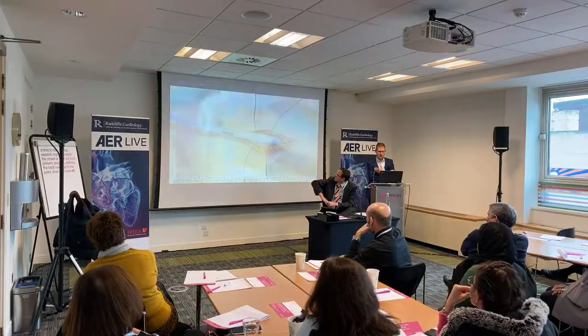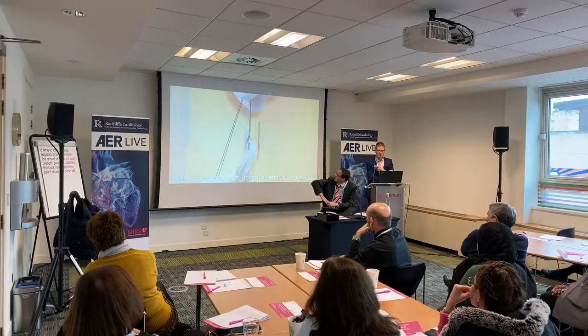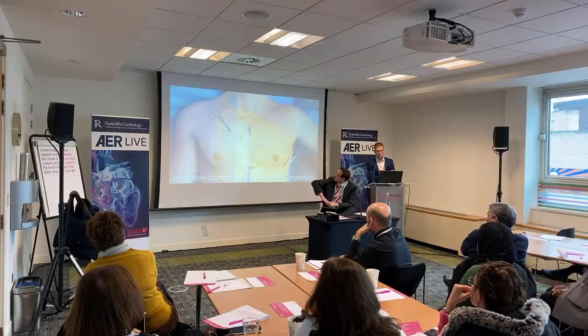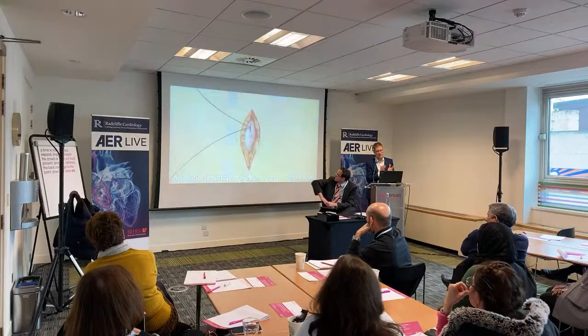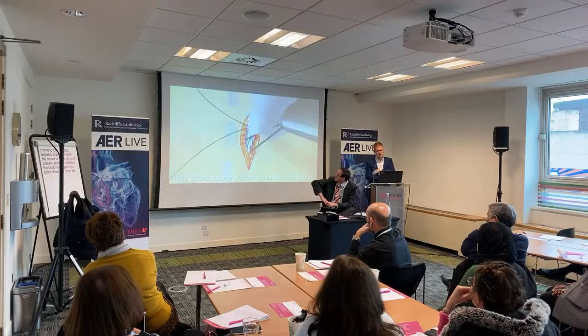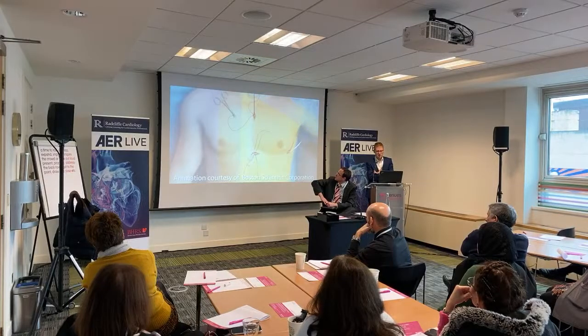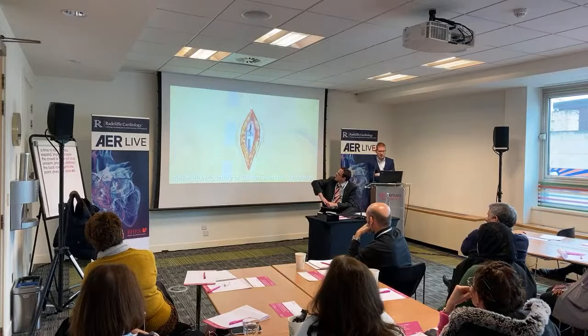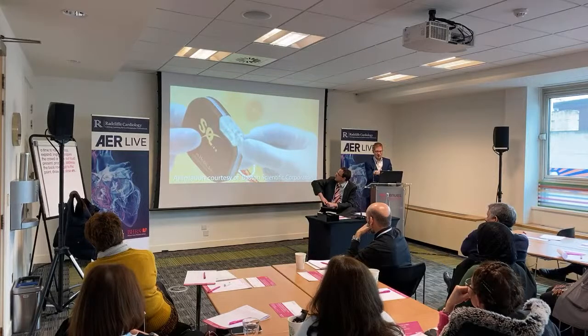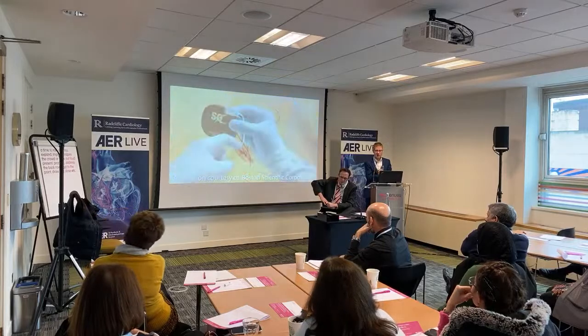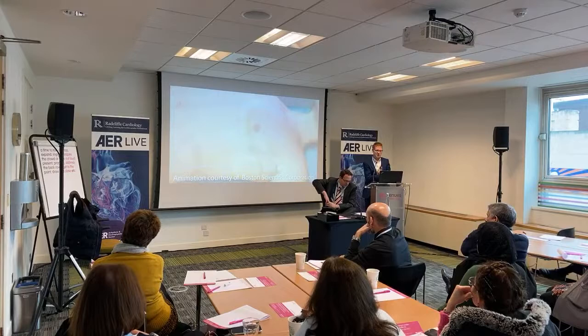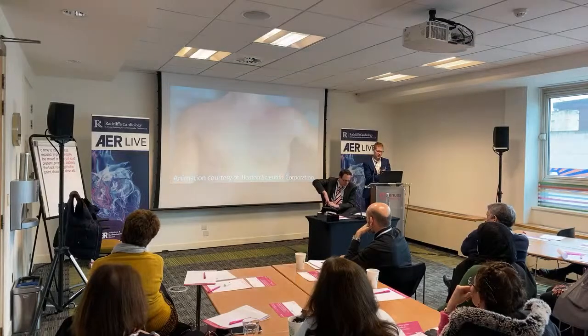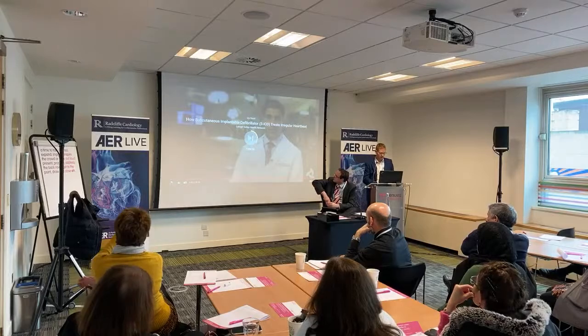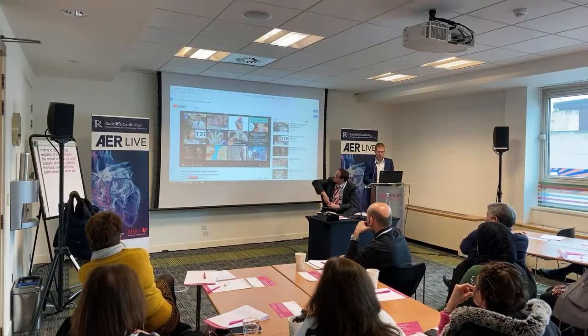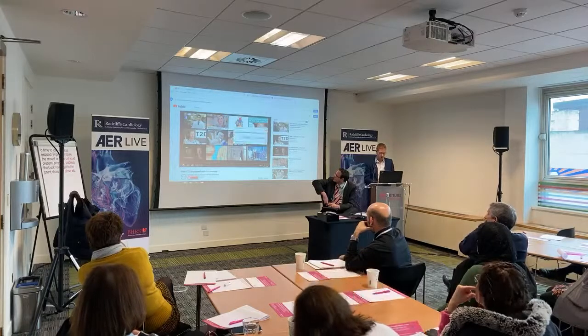And the advantage is there are no leads within the body, so you don't get any problems of subclavian thrombosis or the leads wearing out, because obviously a defibrillator lead is quite thick and there's quite a lot of movement in the heart. And so over time defibrillator leads can fail, and they tend to be the weak points, whereas with this system there's very limited movement. The disadvantage to this system is that it can't at present deliver anti-tachycardia pacing. So a lot of patients who go into ventricular tachycardia can be treated with pacing the heart out of ventricular tachycardia, which avoids the need for shocks.